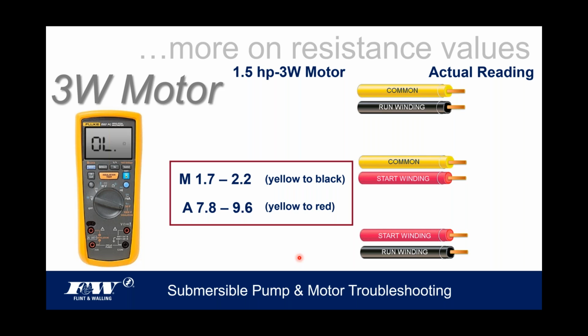So again, if we were to take this 1.5 horse 3-wire motor and we were going to run a test on it, the very first thing I'm going to do is put my probes on the yellow and black wire, and I get a reading on my meter, and it's 1.8. Well, when I look over here at the range, it's within range, 1.7 to 2.2, so I'd give that one a good grade. By the way, if you come through this whole exercise and everything's in range, that's probably an indication of a good motor. But we're talking about troubleshooting bad motors here.